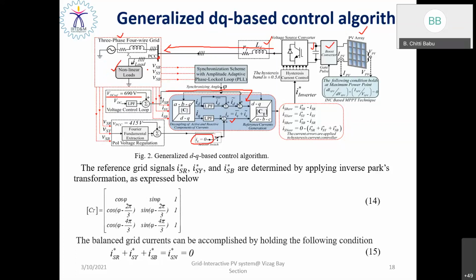But whenever the grid is under abnormal condition, or when the grid is connected with a heavy electronic load, then it needs the support of reactive power. Then IQ must not be 0. So we have an IQ and ID component. Again, that ID and IQ must be transformed into ABC using the Park transformation. That is the way we generate the reference current, right? Then the generated reference current is compared with the actual grid current, and the error will be generated.